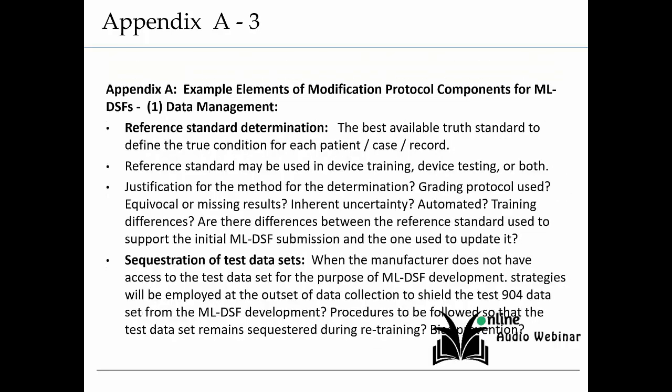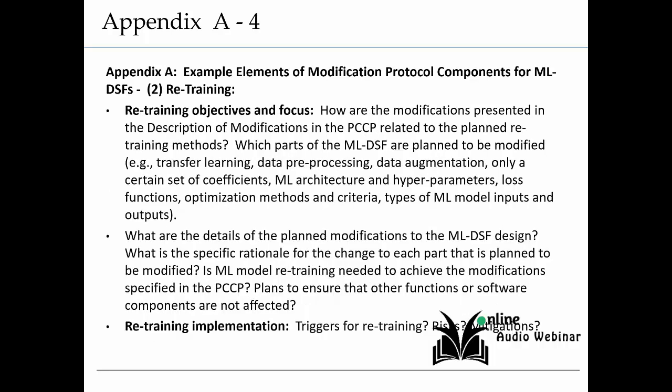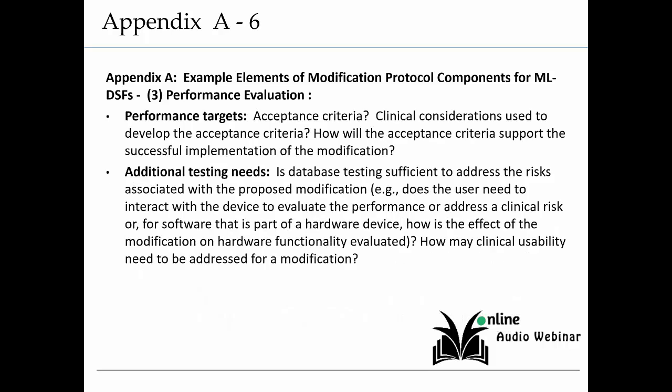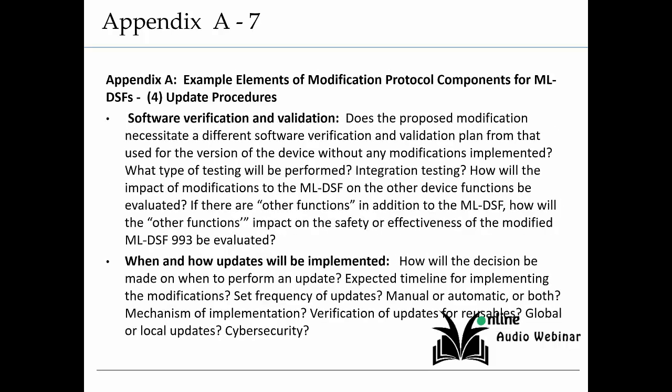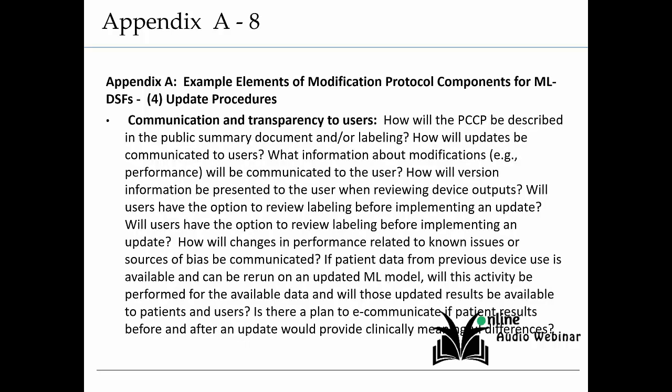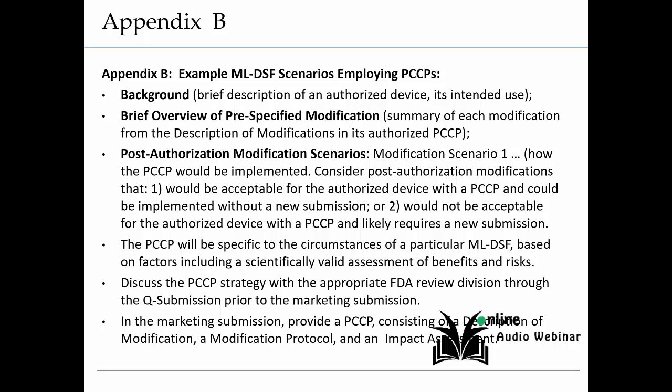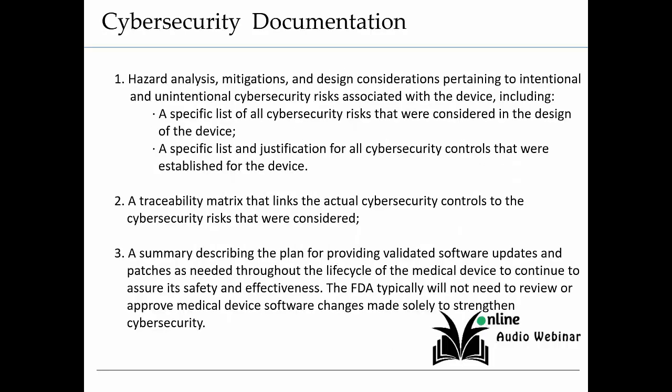Data management issues, reference standard determination, retraining and implementation. And think about that as the retraining of your AI. Triggers for evaluation where necessary, metrics, performance targets, additional testing needs, update software verification and validation, and of course communication to the user. And a monitoring plan, that's post-market monitoring. It's required virtually of all devices. Used to be just implants, but some of the information to provide in the PCCP as well to flesh it out.